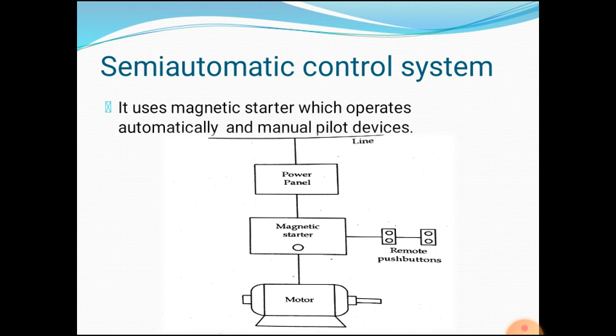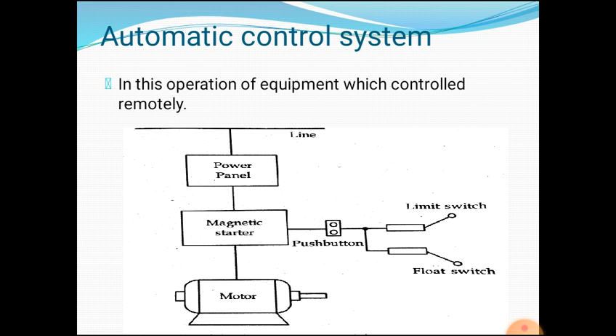Automatic control system. In this, the operation of equipment is controlled remotely. An automatic controller is a magnetic starter or a contactor whose functions are controlled by one or more automatic pilot devices, for example liquid level, pressure, flow, flow of water. And this is the diagram of an automatic control system which consists of line, power panel, magnetic starter, motor, push buttons, limit switches and float switches.